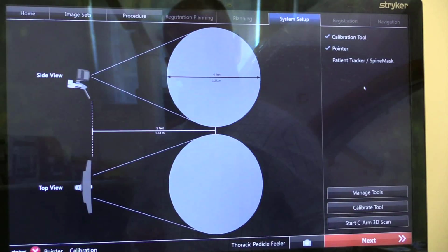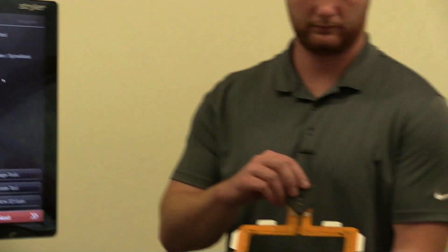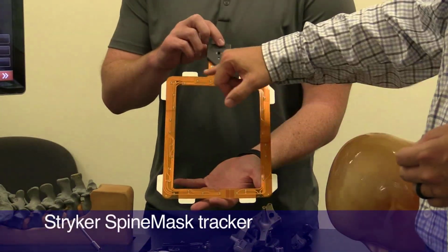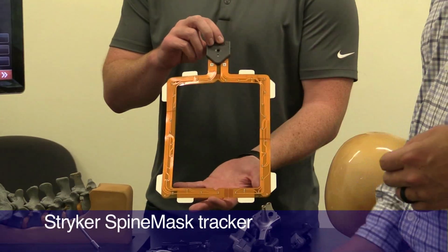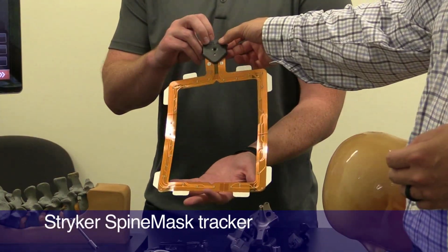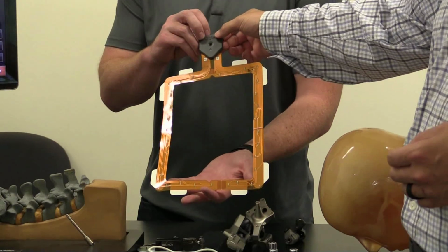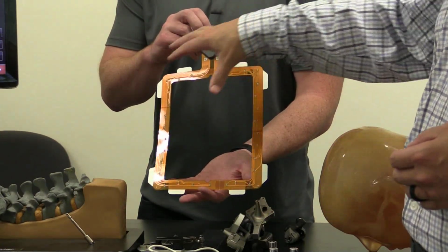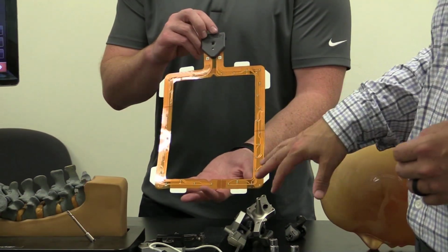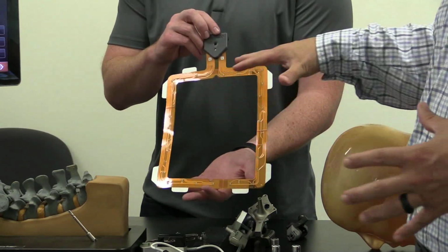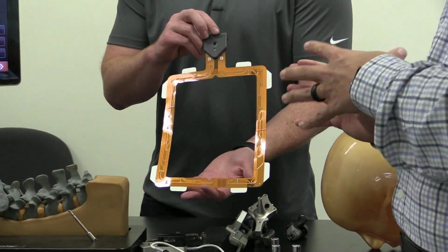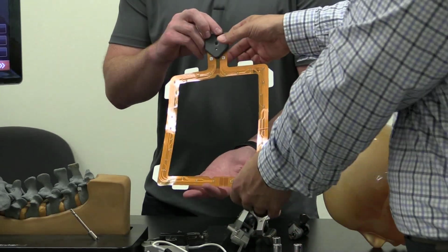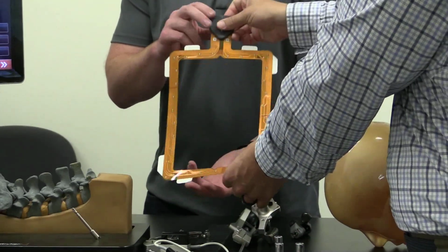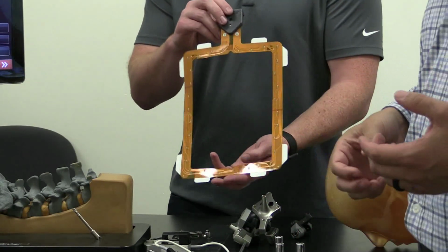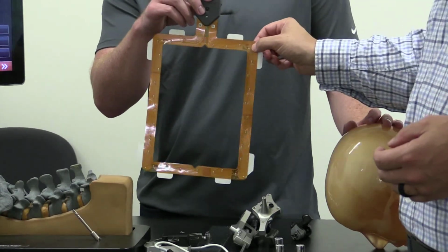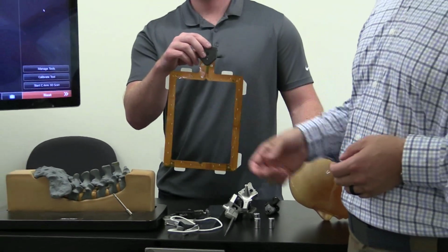So here's the spine mask, which is one type of tracker that we have. We have 31 light-emitting diodes that are powered centrally by this communication unit. This communication unit is sending and receiving information. When we turn this on, no matter where its shape is, once it originally gets captured, whether it were here or even here, it creates what we call a rigid body. So it determines where the X, Y, and Z is of each individual one of the 31 LEDs.